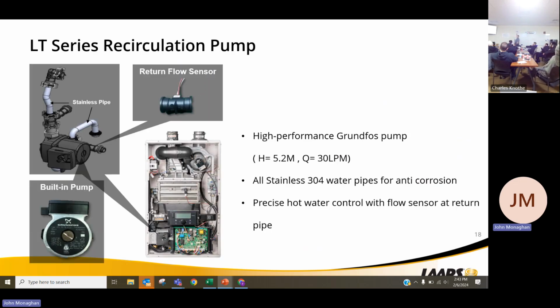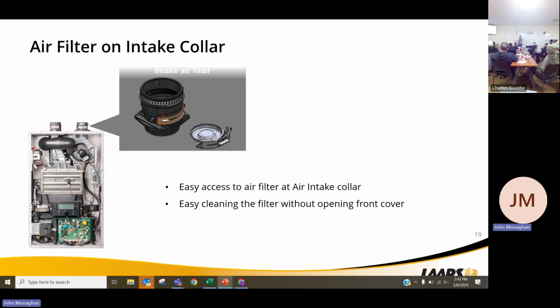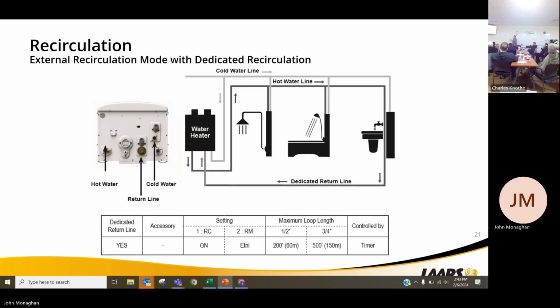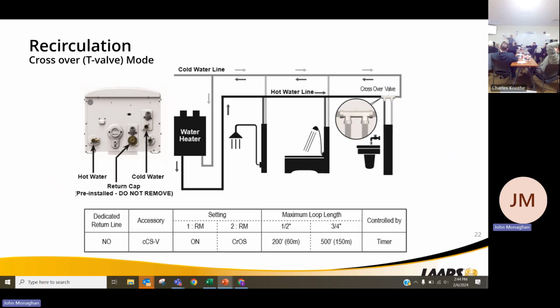So the recirculation pump, it's going to have its own built-in recirc pump. You're going to have your return flow sensor. The pump's going to be a Grundfos three-speed pump. And we have a few ways of controlling this recirc pump. Our recirc, this is doing standard recirculation line, crossover T valve, which is going to be most of our homes where you don't have a dedicated recirc line.